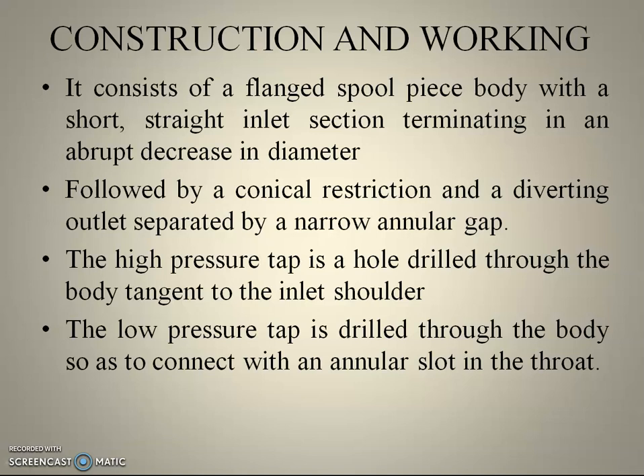Now for construction and working: it consists of a flanged spool piece body with a short straight inlet section, terminating in an abrupt decrease in diameter, followed by a conical restriction and a diverging outlet separated by a narrow annular gap. The high pressure tap is a hole drilled through the body tangent to the inlet shoulder. The low pressure tapping is drilled through the body to connect with an annular slot in the throat section.